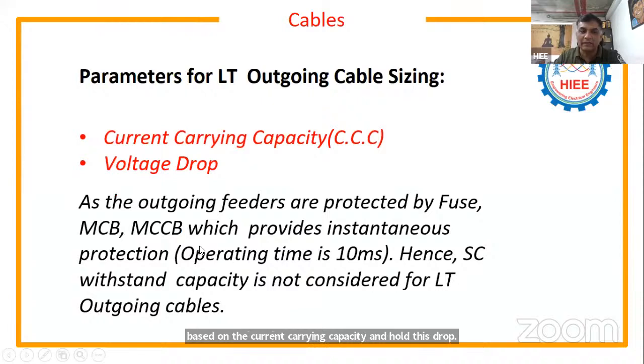Okay, I told you here very clearly. As the outgoing feeders are protected by fuse, MCB, MCCB, where MCB stands for miniature circuit breaker and MCCB stands for molded case circuit breaker, which provide instantaneous protection. Okay, instantaneous protection means the operating time is less than 10 milliseconds. Hence, the short circuit withstand capacity is not considered for LT outgoing cable. This is a very important point in cable sizing calculation.